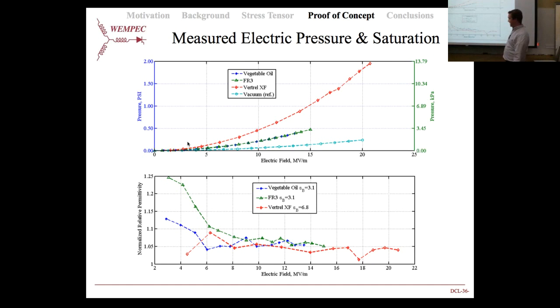And so one of the limitations with oils is, while they provide great breakdown strength, we can get up above, right in here, around 15 kilovolts per millimeter, one problem is that their permittivity is relatively low. Some of these other oils, or not oils, but this is a dielectric liquid provided by DuPont, and that one has a permittivity of around 7, so twice that of oil.